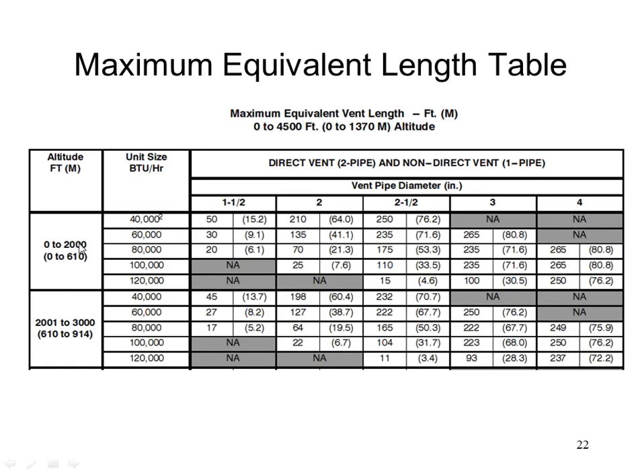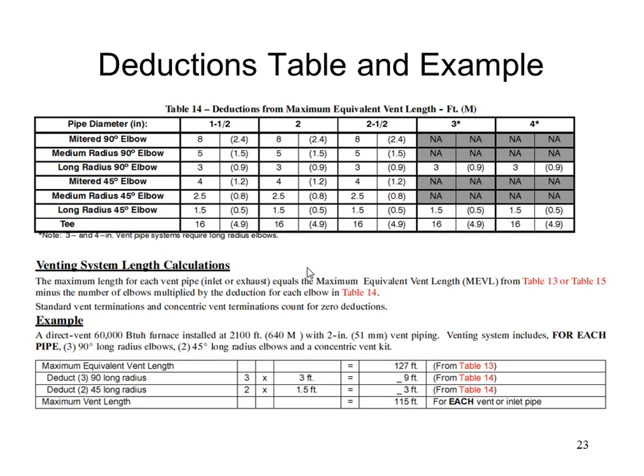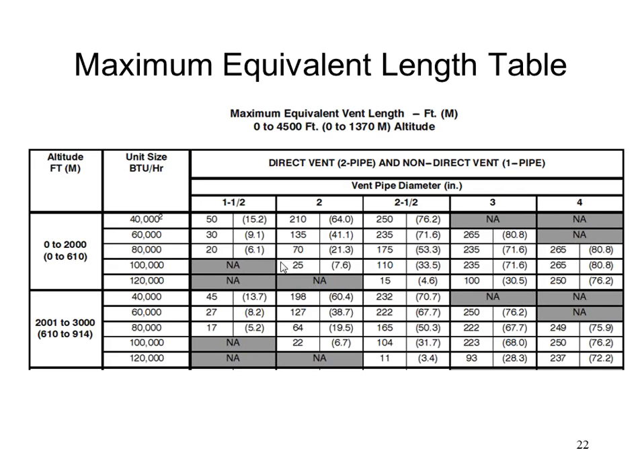So if you look at that, you take a typical, let's say 100,000 BTU furnace. This table is telling me I cannot vent that 100,000 BTU furnace in 1.5-inch pipe. I could vent it in 2-inch pipe up to 25 feet, which might be fine if the furnace is right near the exterior wall. By the time I add the penalty for the elbows and so forth, it would get chewed up pretty quick. So here gives you an example of the elbows. A tight radius elbow is 8 feet. A long radius elbow is a 3-foot penalty.